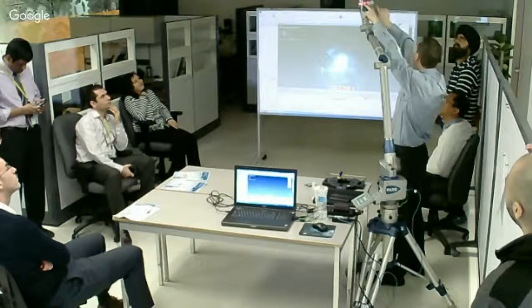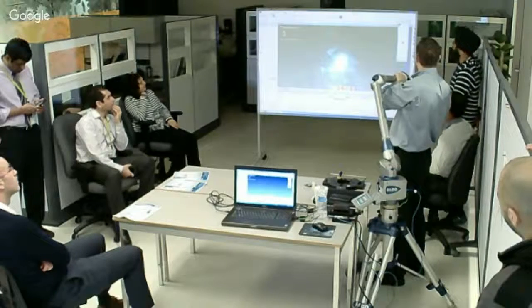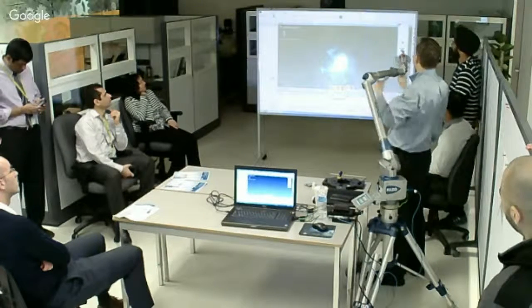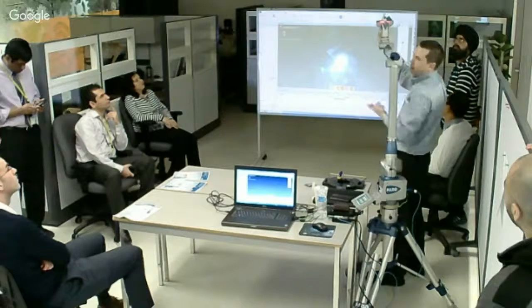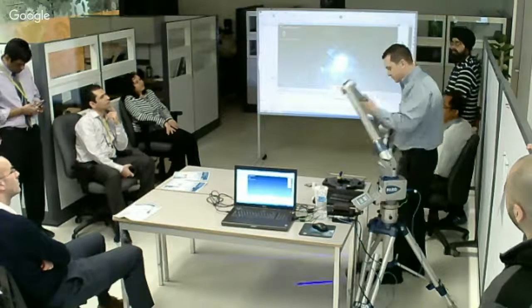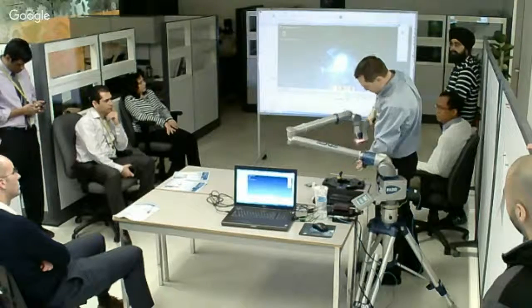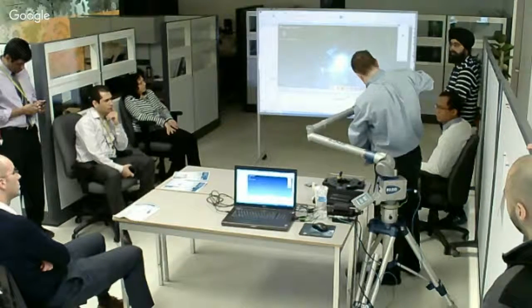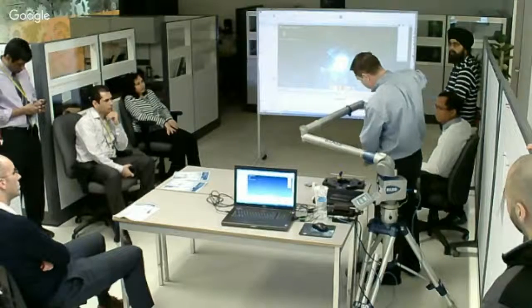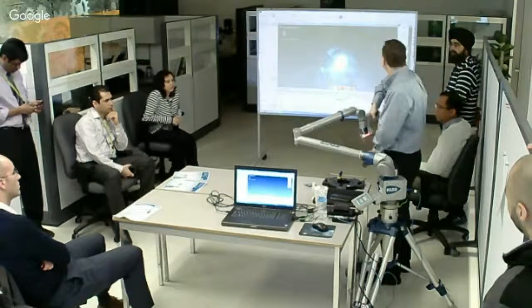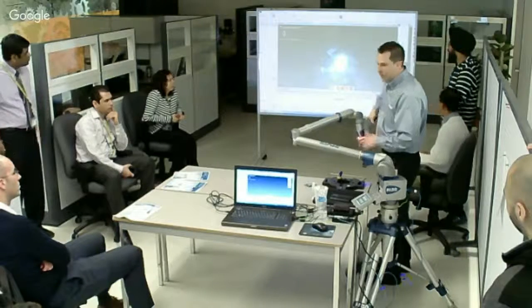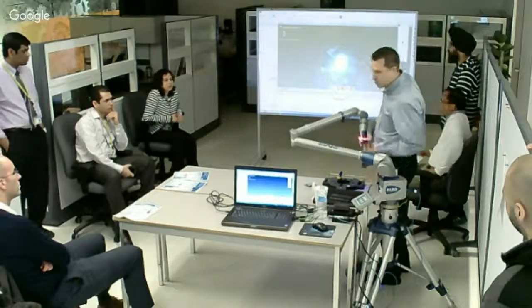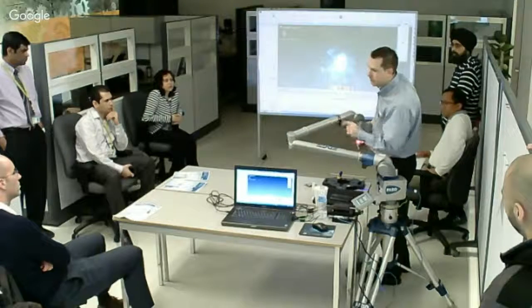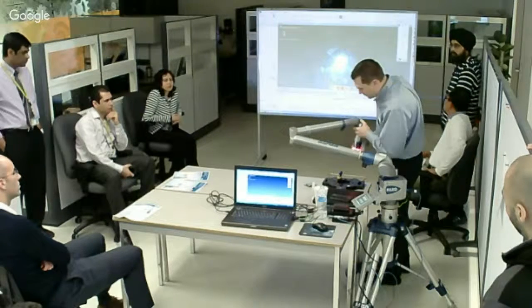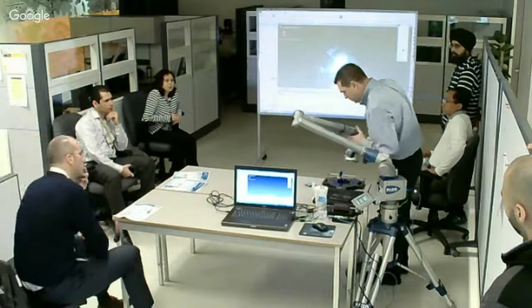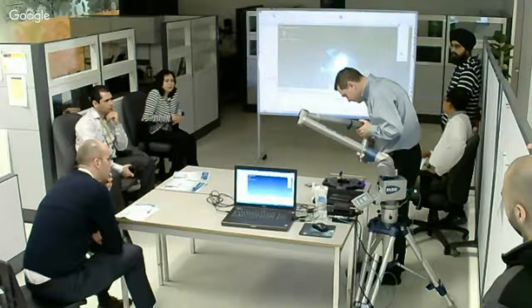Right now on here, I'm showing red, or if you look over here, that's the range. The green, it's past its range. So red, I won't actually collect data if I press the button. I want to be keeping it on top of each other as best I can, intersecting. And you can see how once I do that, it goes green, the arm itself. So I've got visual on the computer to say I'm within range. I got the visual on here, and also the sound. So if I'm here, it won't collect, whereas when I'm here, you'll hear it actually collecting the data set. So I'll just do a pass over this part here. I just press the green button to start.